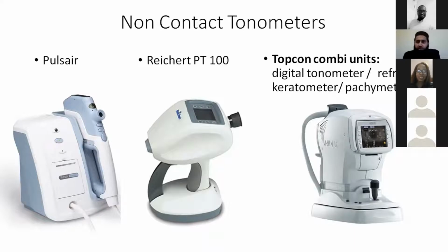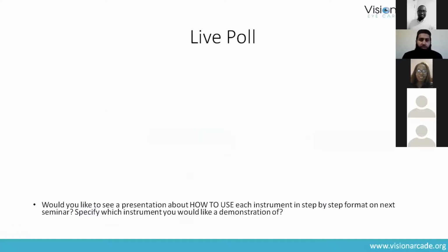Again, these non-contact tonometers, the advantage of that is it does not need any anesthesia. But again, I would say that iCare doesn't need that either. But these ones, they make the patients jump and they don't like it, and their accuracy is also questionable, and we have to double check with Goldmann regardless. However, this is something that is affordable, and it is readily available in most of the practices. So yeah, that's non-contact tonometers.